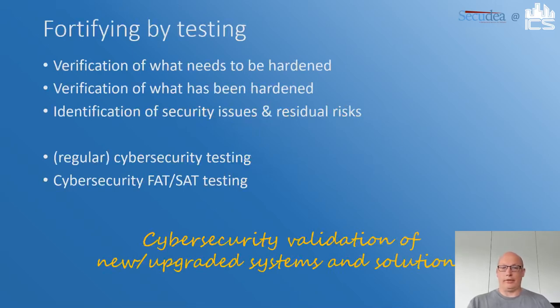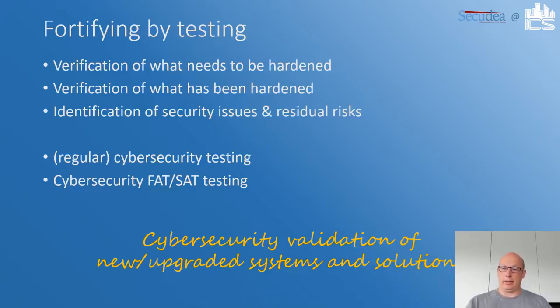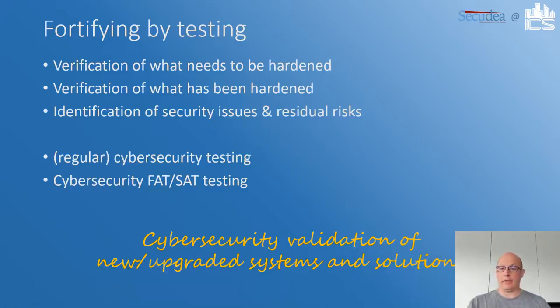We can also fortify ICS systems by performing security testing — by knowing your weaknesses and then depending on those weaknesses, doing hardening or not. Fortifying by testing is: verification of what needs to be hardened before hardening, verification of what has been hardened after hardening, and identification of any other security issues and residual risks. Cyber security FAT testing is one of the few times in an ICS environment where you can go all the way with security testing, because it's in an isolated test environment.